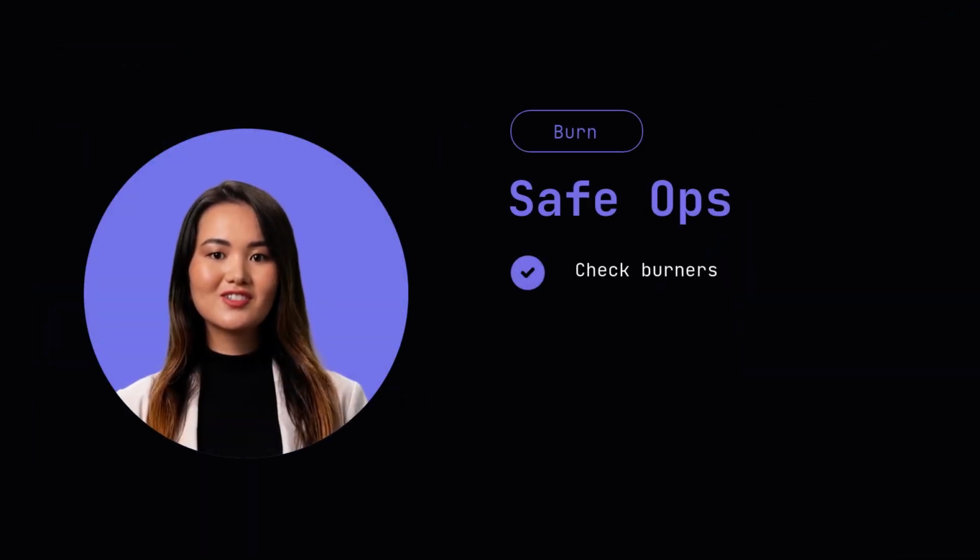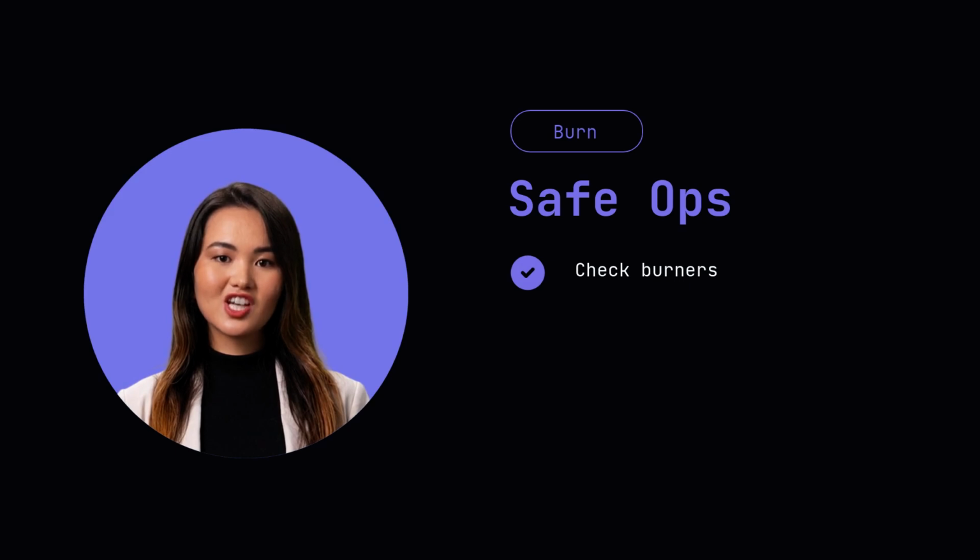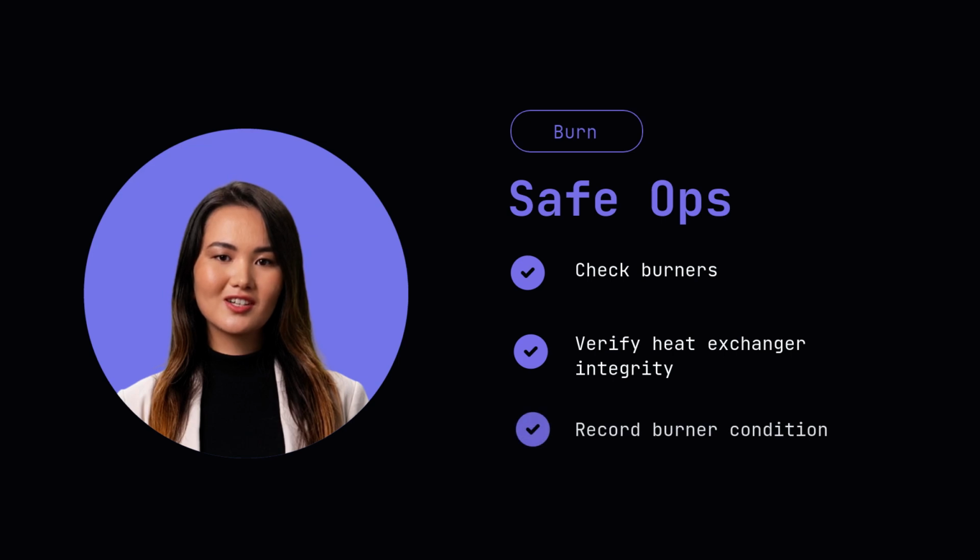Ensure burners and heat exchangers operate safely. Check burner condition and flame appearance. Verify heat exchanger integrity and carbon monoxide levels. Record burner condition and attach photos. Comment on any repairs or cleaning needed.